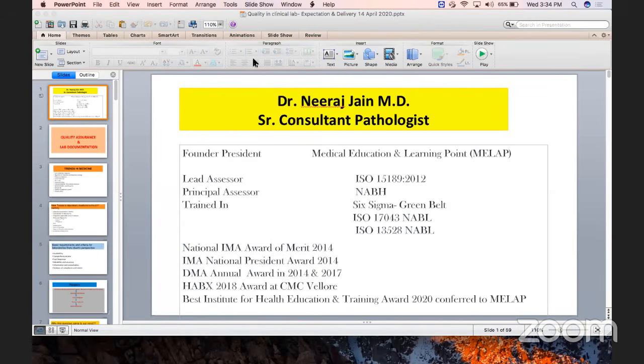Sir, one last question. How long should the records of maintenance, calibration, and QA be retained in the laboratory? As per ISO 15189, clause 5.3.1.7, this should be maintained for the whole life of the instrument. Life of the instrument. Not IQC and IQAS. This relates to instrument maintenance and purchase, for the whole life of the instrument. For IQC and IQAS records, if you are going for accreditation, you have to follow the recommendations of the accreditation body, and otherwise maintain these records till the next accreditation, or at least 3 years.